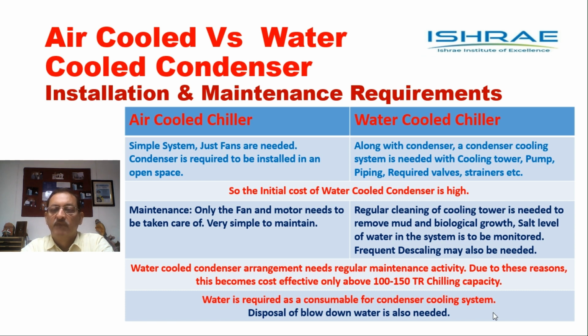On the other hand, when we have water cooled chiller and the condenser cooling system along with that, that will have a cooling tower, a lot of mud gets accumulated, the dust in air that gets accumulated in the form of mud, and that is required to be removed at regular interval. There is biological growth that takes place, which is required to be cleaned at regular interval. Then, in addition, we also have to be careful about the salt level in water, because once the salt level goes up, the water can become very corrosive and it can harm the system. And to ensure that the salt level remains in control, we have to do regular blowdowns.